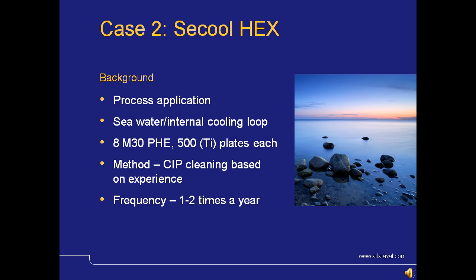The second case is within a process application where the customer uses seawater to cool an internal cooling loop that cools the rest of the factory. This is usually done when seawater is being used for cooling, so that you can isolate the contact of the seawater with a piping by just allowing it to come in contact with a set of heat exchangers, and then the rest of the piping can be done in stainless steel.